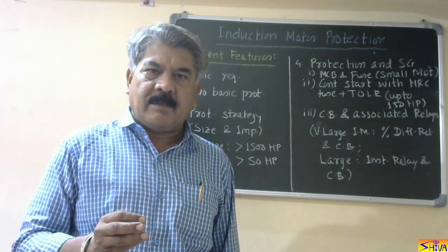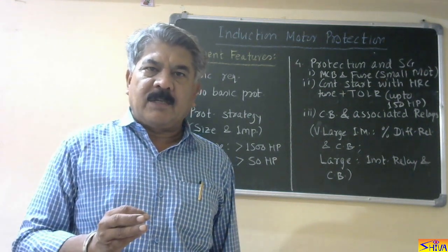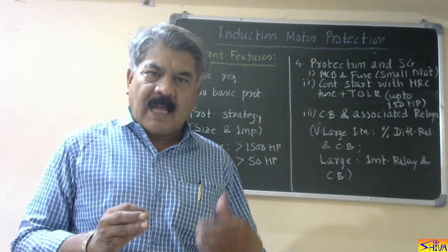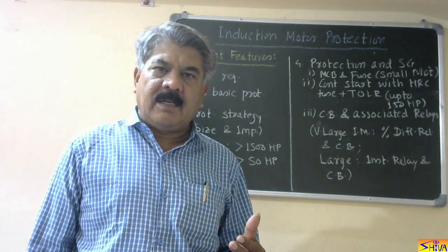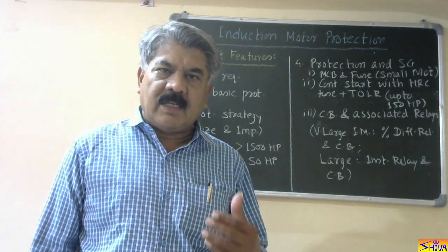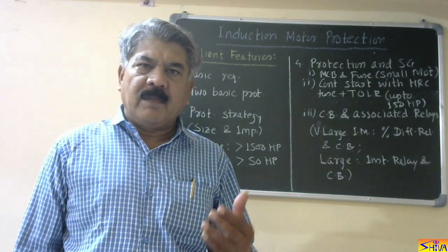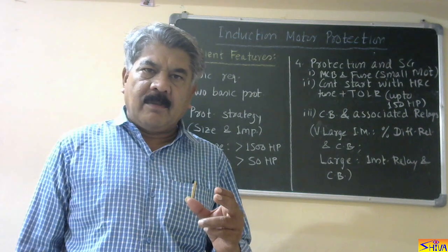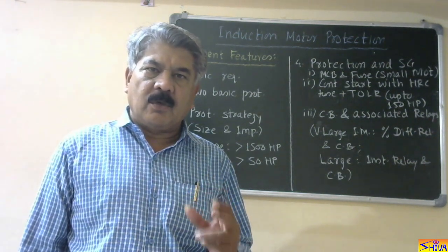That is first requirement. Second, every induction motor is permitted to take some overload, and the time for which the over percentage overload is permitted reduces with the degree of overload. Higher the overload, less is the time permitted. So during permitted time of the overload condition, the protection system should not operate.